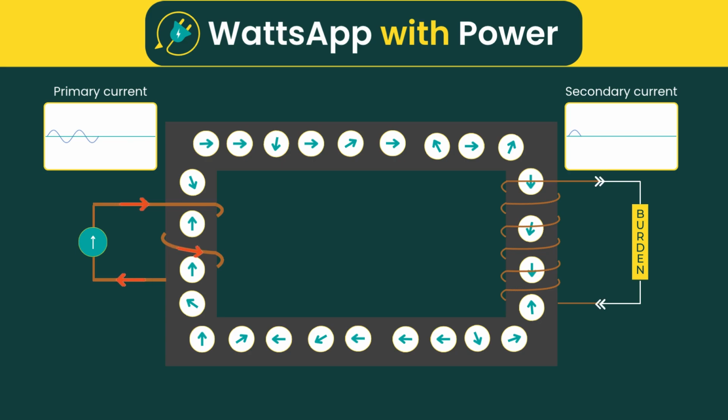In the next half cycle, the current reverses direction. The magnetic field now flips, and the dipoles start aligning in the negative direction. Again, because there are enough unaligned dipoles left, the flux keeps changing throughout the negative half cycle, and the CT continues to track the current accurately. As long as the magnetic field stays within limits, the core does not saturate, and the CT behaves as expected.